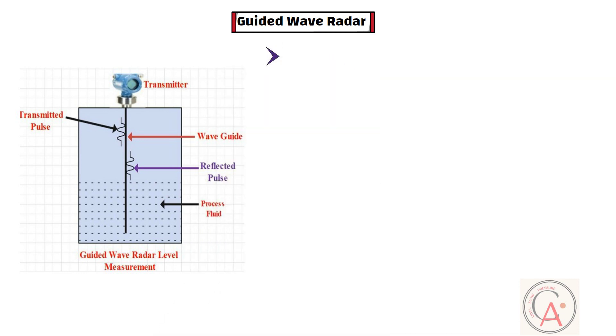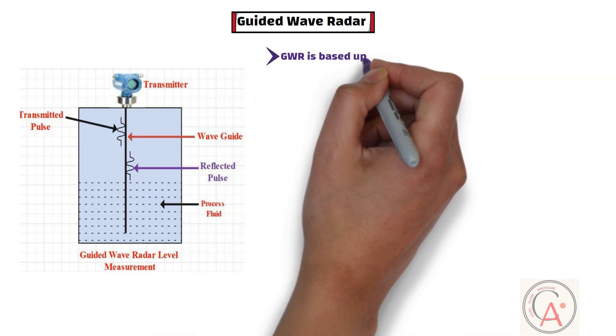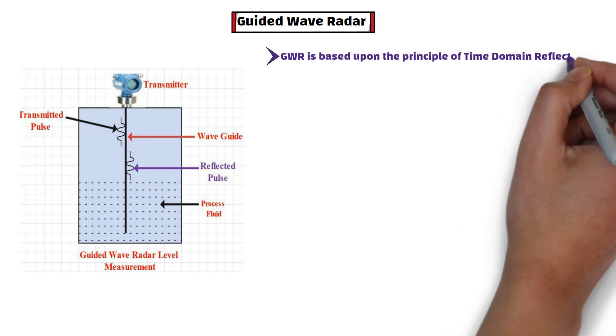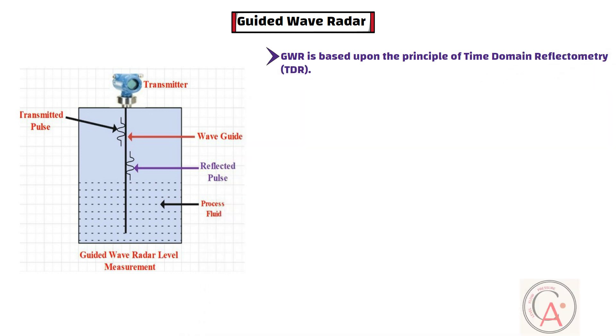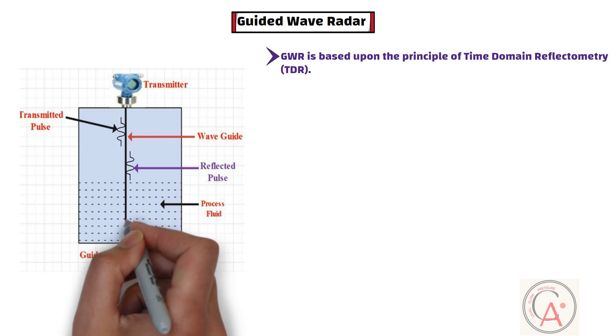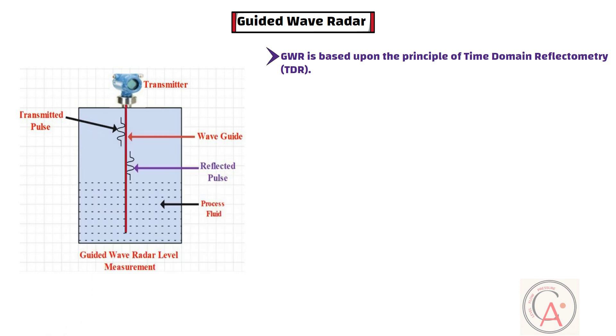Guided wave radar technology is based upon the principle of time domain reflectometry, which is an electrical measurement technique that has been used for several decades in various industrial measurement applications. In this method, a low-energy electromagnetic pulse is guided along a probe. When the pulse reaches the surface of the medium being measured, the pulse energy is reflected up the probe to the circuitry, which then calculates the fluid level from the time difference between the pulse sent and the pulse reflected.